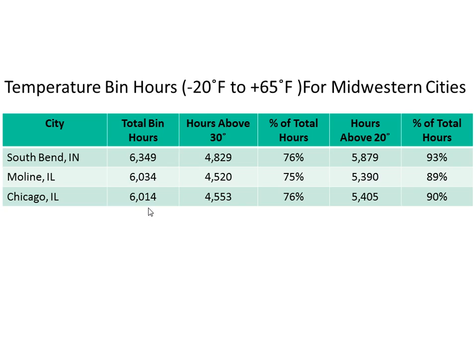So it is a little bit depressing if you think about where we live and how much heating we have to do. But that's the way it is. If I look at hours above 30, or more properly, between 30 and 65, so how many heating hours do I have between 30 and 65 degrees outside, I have 4,500 hours in Chicago. That's more than half of the hours of the year. More than half of the entire year we spend between 30 and 65 degrees outside. That accounts for 76% of our heating hours. So 4,500 of the 6,000 are above 30.